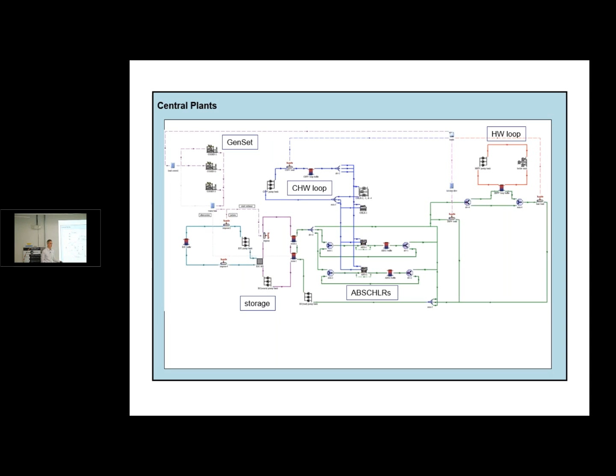But there were so many issues about how should we run these things. Should they be run to meet an electricity load, or at some other efficiency point? The campus should buy electricity at times and sell electricity at times. Should we run these things in order to make waste heat to fire these absorption chillers? Or should we run them at some very low baseline, not meet our electricity needs, use them minimally, because really what these things are here for is helping us save energy in the hot water loop? There are a lot of really fascinating lessons learned from this. Again, the flexibility was really key.